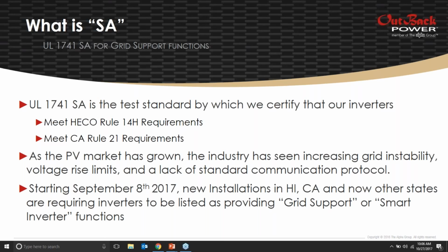So when they did that, it actually caused a reverse effect of a surge. If the grid became slightly unstable, a whole bunch of inverters, if you had a lot of PV in a certain area, would disconnect at the same time, making the situation worse. So here we are, now they're saying, hey, stay connected and support the grid a little bit longer.